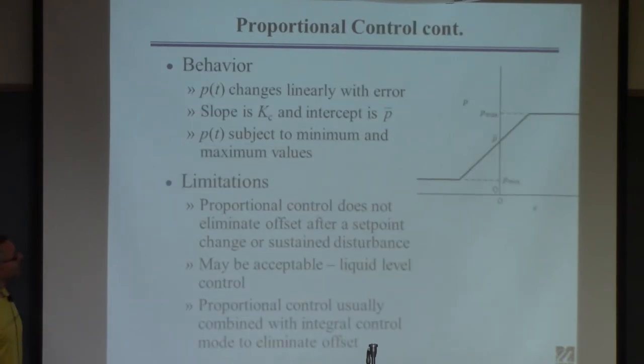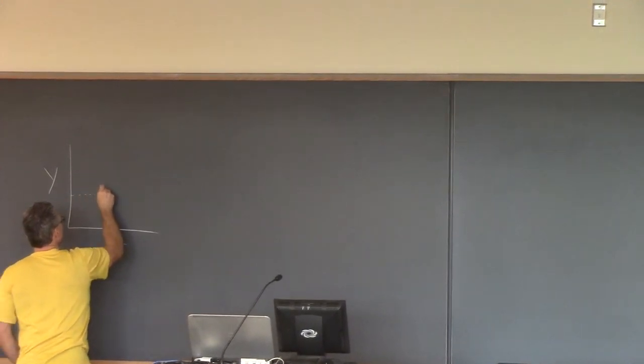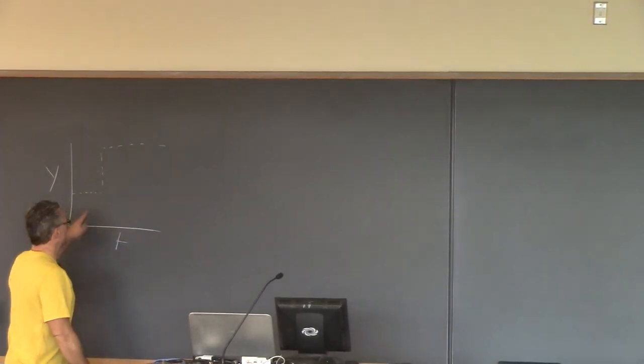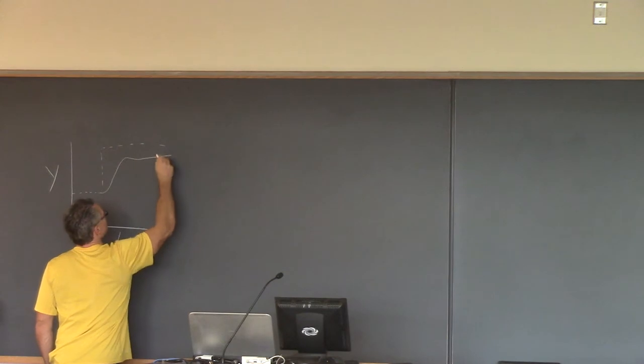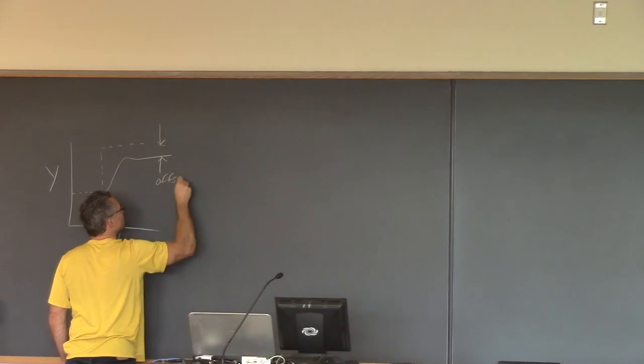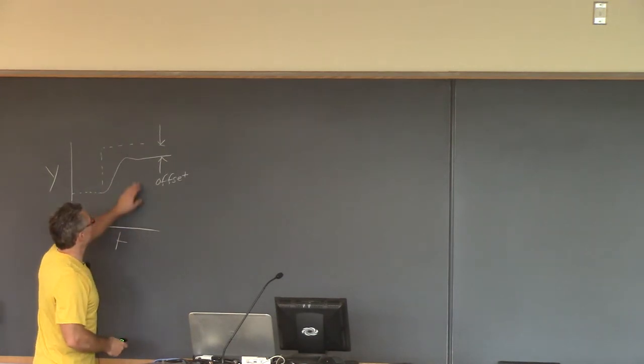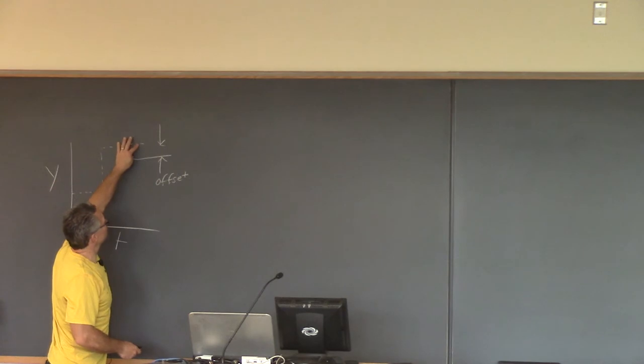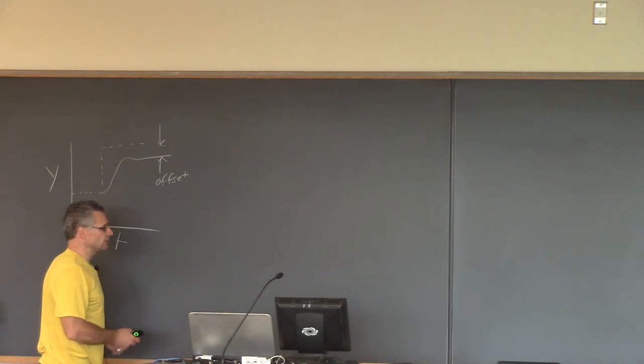One problem with proportional control is it doesn't eliminate offset. If you have a set point change, a proportional-only controller might not actually reach the desired value — the output falls short. This is called offset, and it's quite undesirable for operations people. If the desired temperature is 230 degrees but the actual is 210, they'll assume the controller isn't working and shut it off.